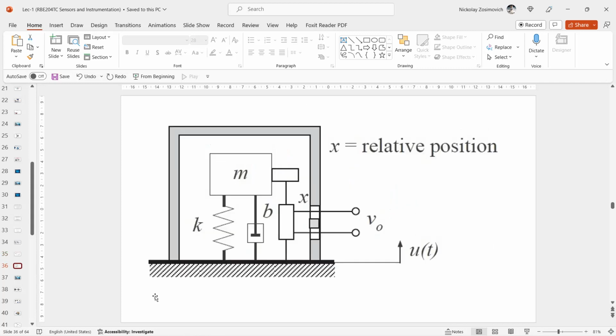Some variables can be derived from the others by electronic signal processing. Speed and acceleration can be measured using a displacement sensor by differentiating its output signal once or twice, respectively. Conversely, by integrating the output signal of an accelerometer, a velocity signal is obtained, and by a second integration, a position signal. Obviously, the performance of the final result depends on the quality of the signal processing. The main problem with differentiation is the increased noise level, in particular in the higher frequency range. An integration may result in large drift due to the integration of offset.